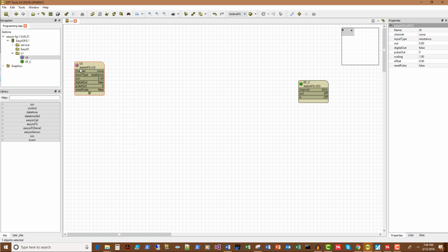We're going to go back over here to UI. And we're going to call this ZN underscore T, so zone temperature. We're once again going to pick UI1 here. Now we see this is a type resistance. Now, not with every controller software, but with this controller software, we're going to have to go and take this resistance and put it into a temp table. Depending on whose software you're using, you may run into where they let you manually set your table or automatically set your table in the input. Here we don't have that option.